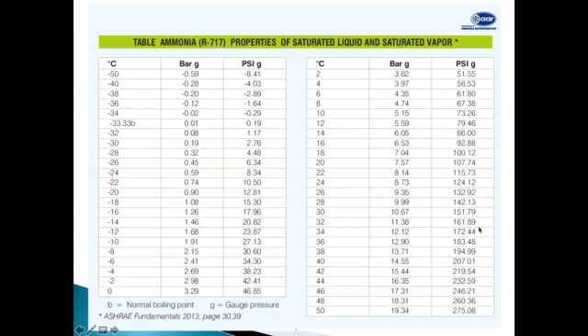He went there. He found that the discharge pressure, when we started the plant, was around 15.5. Now it had come down to 13.2. So discharge pressure 13.2 is correct considering the ambient conditions of that particular plant, and since there was no air, no air was coming out of the purger. But the customer was not ready to accept that there is no air in the plant. So I said, you bring air into the plant and we will prove that the purger is working.